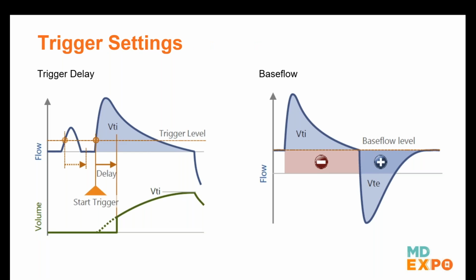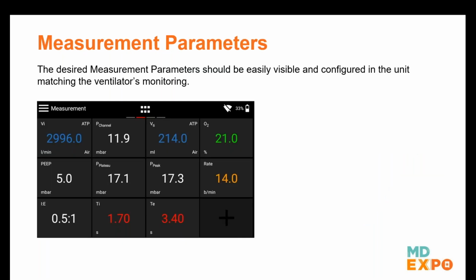Okay, the last thing on the settings side: we talked about gas type and gas standard with Kerwin, and now trigger settings. The last thing Kerwin mentioned in his introduction, and I'm not going to talk more about it because you explained it very well, is that we need to make sure that we are looking at the right values on our gas flow analyzer, and that we have it set up in the same unit of measurement as on your ventilator. So you're comparing apples with apples, or banana with banana. Again, there are different terminologies. Sometimes the ventilator manufacturer calls something different than your analyzer, so you need to know that and make sure that you look at the right value.